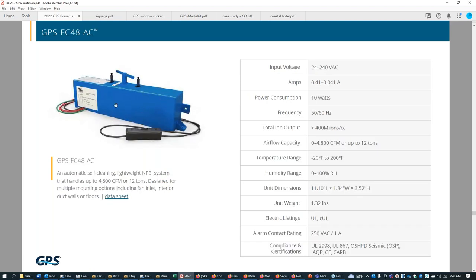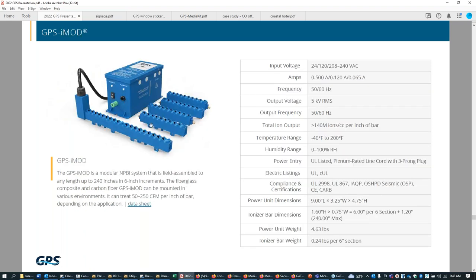This device I showed you in some of the install photos can be mounted on the inlet of a fan venturi. This can go on rooftop units, any sort of air handler where you have room. And this is our iMod. This is an evaporator coil mounted product. We use this a lot for odor control applications, for keeping coils clean. This can be scaled up based on the width and height of the coil.